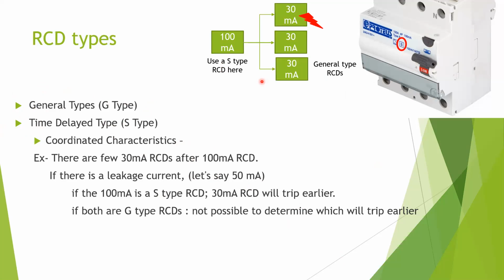This is also one thing RCDs have different from the MCBs. MCBs are always tripping according to some time curve. There's instantaneous protection, we are coming to that later. Usually, RCDs are instantaneous devices. So what happens is, if you have a leakage current, it trips your circuit instantaneously once it detects it. So an RCD should be an instantaneous device.